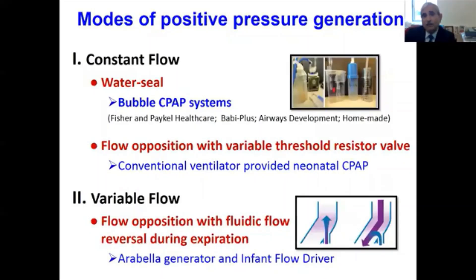Now that I've spoken about the interface, I'm going to briefly talk about how to generate the pressure. One can use a constant flow system, and the most simple one is a water seal system that utilizes threshold resistor principles, where the pressure is determined by the force applied to the surface area. The generated pressure is independent of flow. Bubble CPAP systems such as Fisher and Paykel, Babi Plus, Airway Development, and homemade systems are most commonly used.